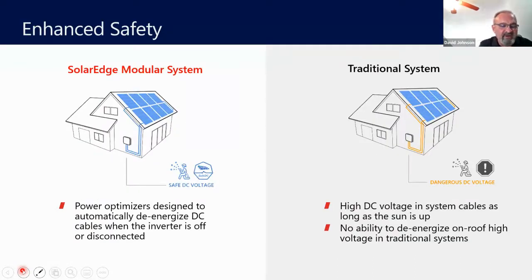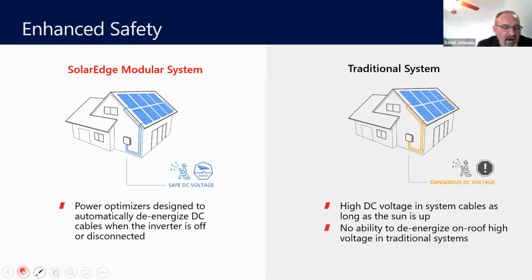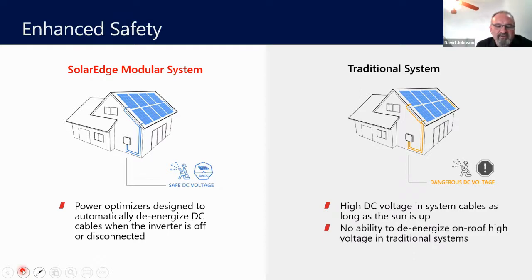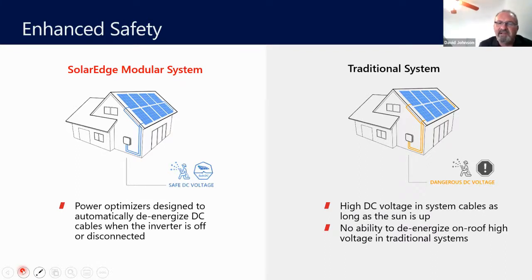There's also a safety benefit. Since there are now power electronics at the module level, the modules can be disconnected if needed. The sun can never be turned off, and in case there's a fire in the building not related to the solar system, firefighters may be reluctant to go onto the roof, potentially causing a complete loss of the building. Even if they are able to shut off the inverter, there's still voltage in the cable at all times. However, in SolarEdge's modular system, they can be de-energized to a safe DC level.